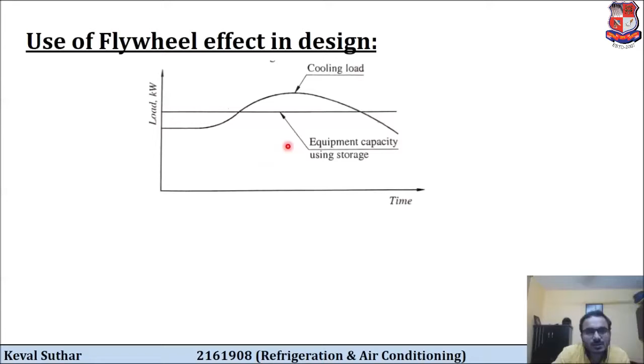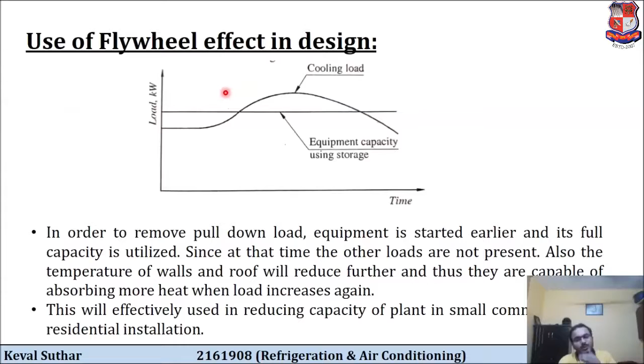Since at that time the other loads are not present, the temperature of wall and roof will reduce further. Once we start our equipment 1 to 2 hours earlier, the wall and roof temperature will reduce because of the early start of our cooling system. Thus they are capable of absorbing more heat when the load increases again. In this way we are using the flywheel effect in design. This will be effectively used in reducing the capacity of plant in small commercial and residential installation.